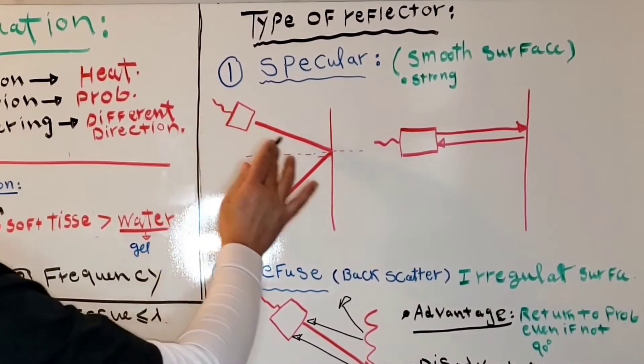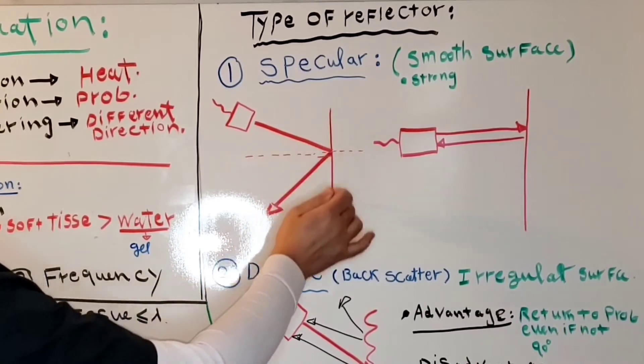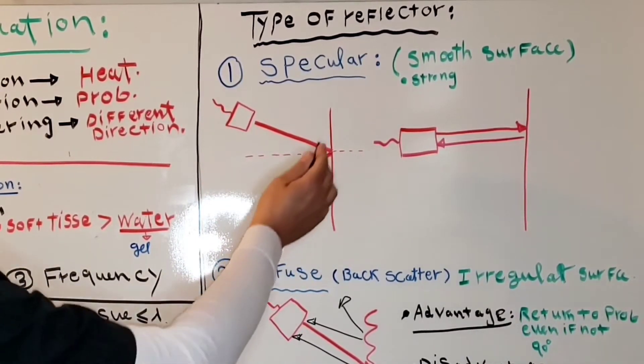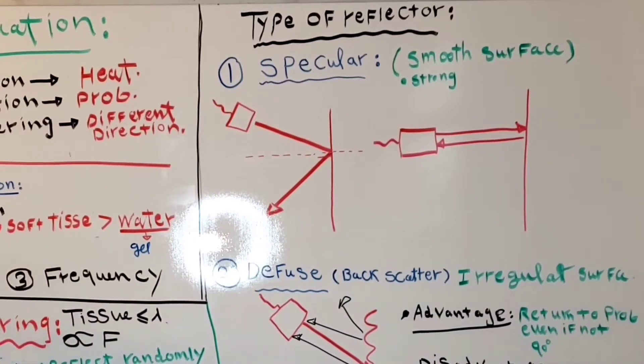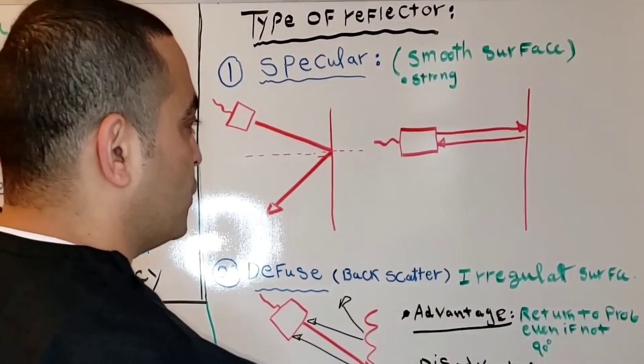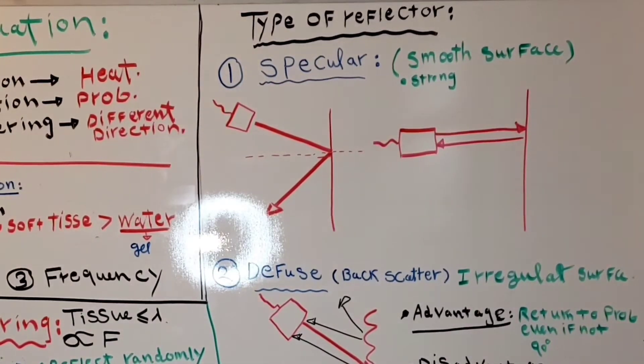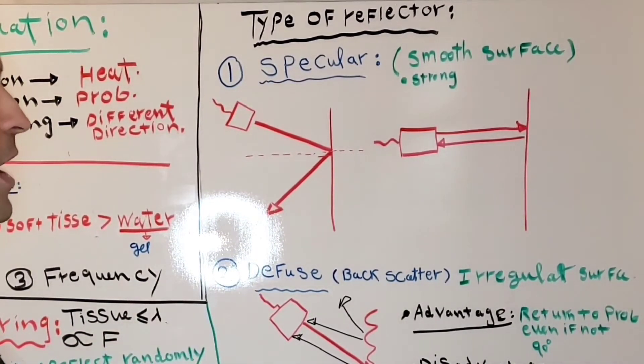A disadvantage of the specular reflector is that it will not return sound to the transducer unless the beam is at 90 degrees — perpendicular to the surface. If the transducer is not perpendicular, the sound beam reflects somewhere else. When it is perpendicular, the reflection returns back to the transducer, but this can cause artifacts. An example is the mirror artifact, which can be eliminated by making the transducer perpendicular.